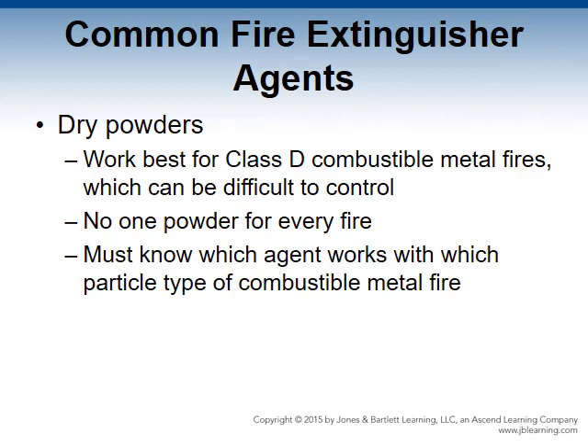Dry powders are the best method for extinguishing Class D combustible metal fires, which can often be difficult to control. No one dry powder works on every fire. Some sodium-based agents form a crust on the burning material to deplete oxygen. Graphite-based agents conduct heat away from the fuel. It is important to know which agent works for which type of combustible metal fire. Some are not used in an extinguisher and are applied by a scoop, shovel, or handle.